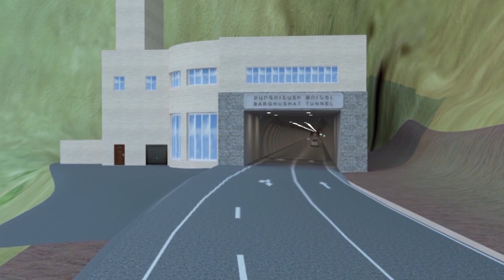The following prevention measures will be ensured: lighting, fire system, escape way, access to escapeway at every 500 meters, layby at every 1000 meters, SOS at every 250 meters, smoke extraction, ventilation. In case of fire, the smoke is extracted by ventilation systems at both ends of the tunnel, inside the smoke extraction duct. People will have an escapeway located under the platform every 500 meters and then an escape route to a safety place.